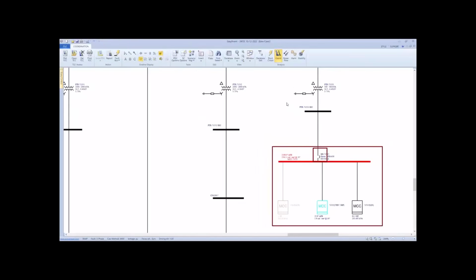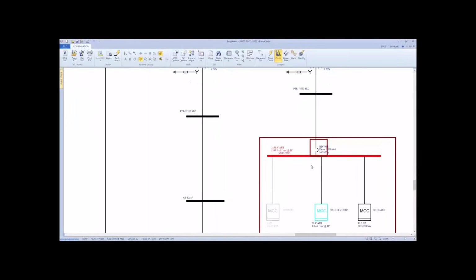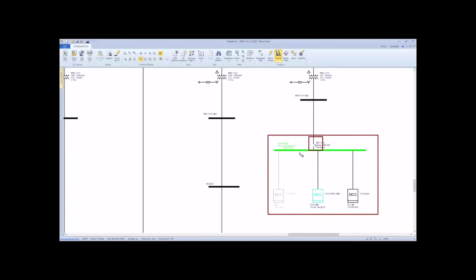Sequence of events, okay, sometimes - in this project I'm working on, we have to work on the protection upstream in order to decrease the quantity of calories per square centimeter, but sometimes this is very, very useful. For instance, if here we have a high arc flash, we can work with this in this way.